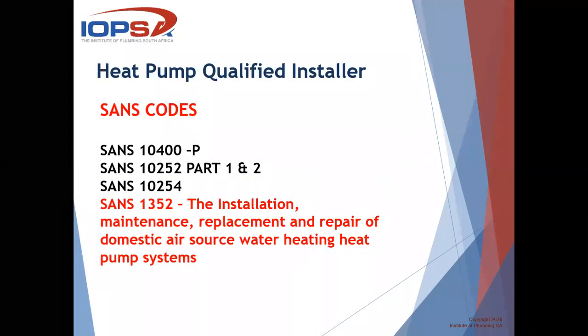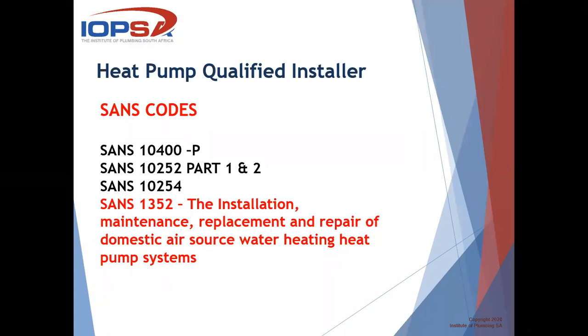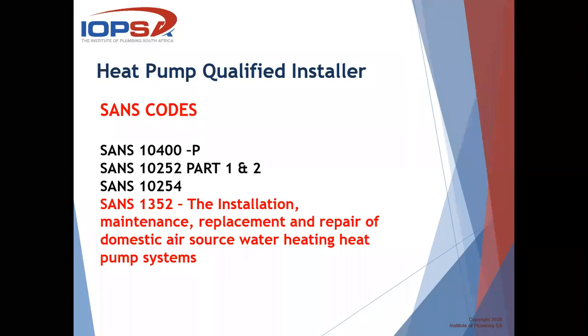In this instance, the SANS codes applicable will be your normal 10400, 10252, and 10254, plus SANS 1352, which covers the installation, maintenance, and repair of domestic air source heat pump water heating systems.